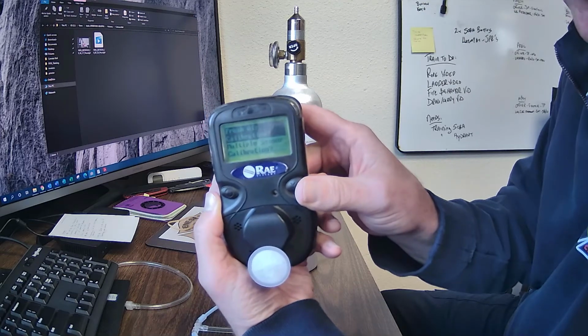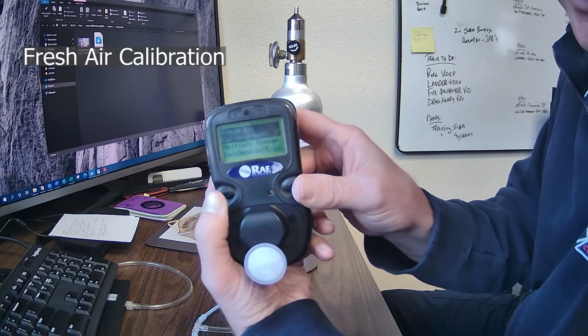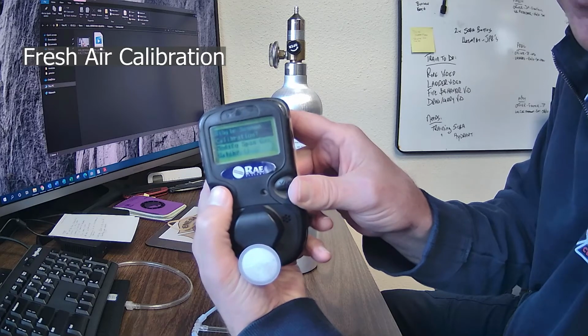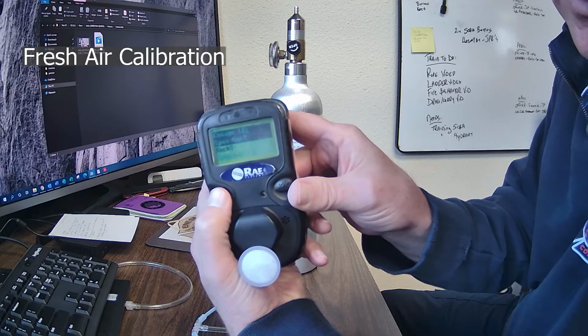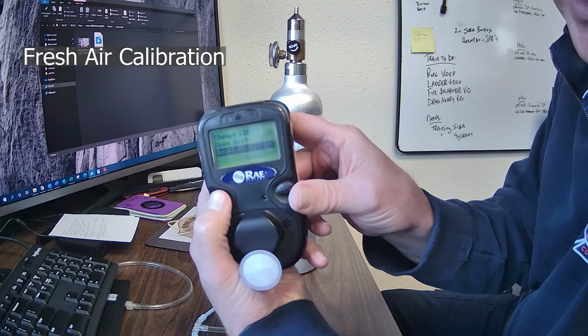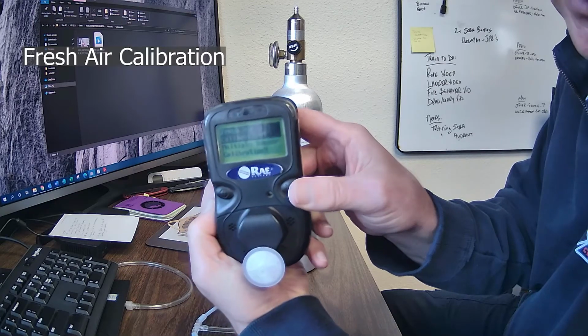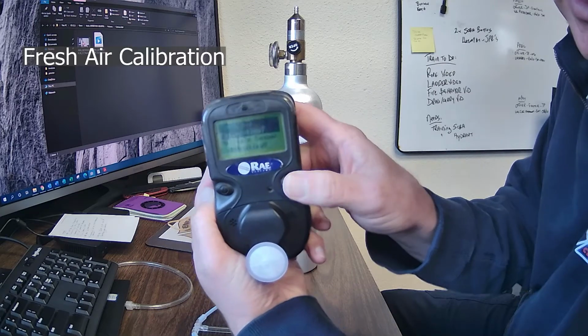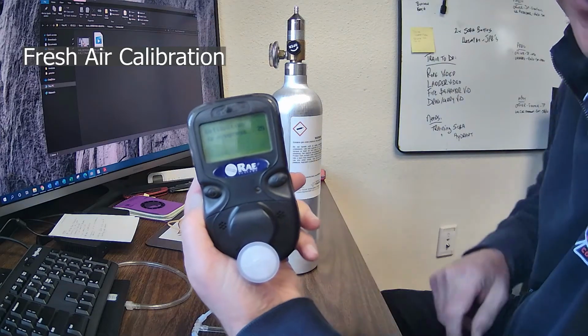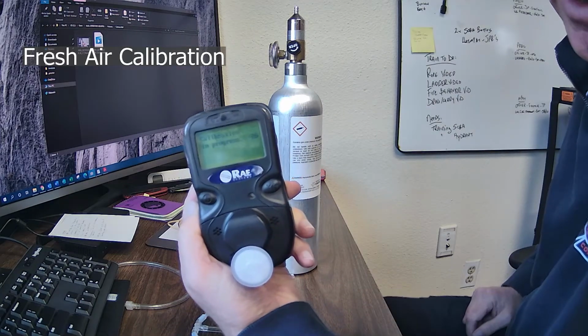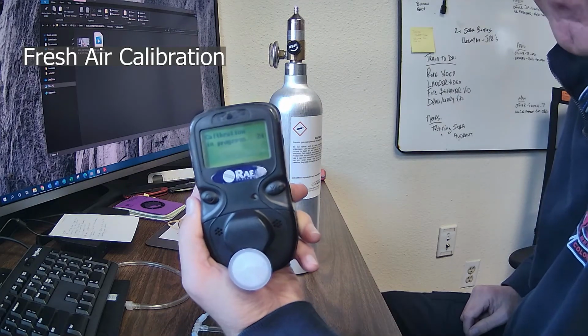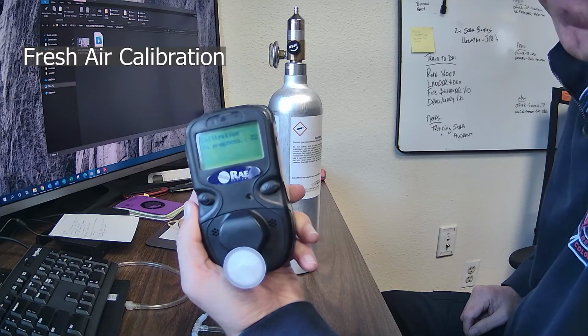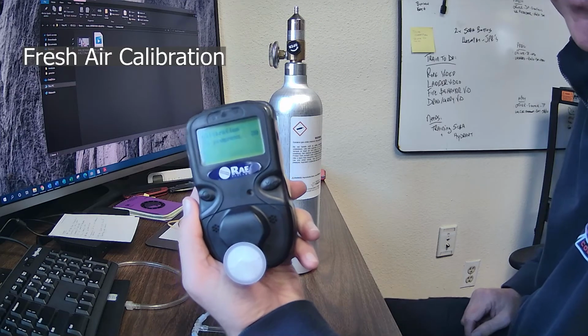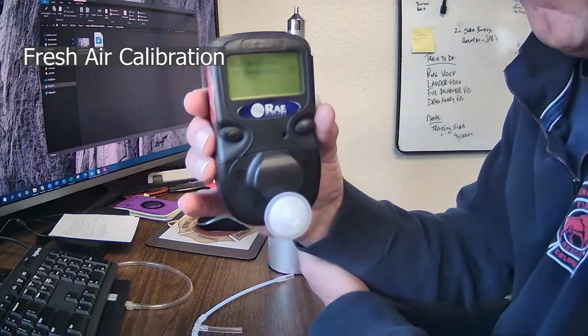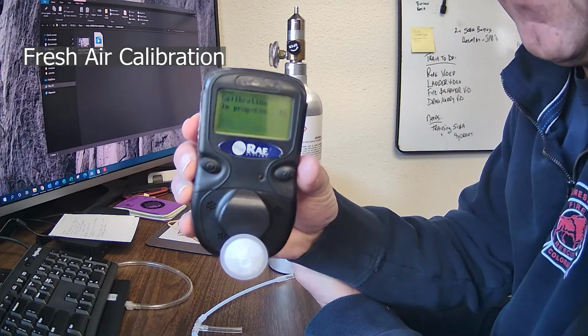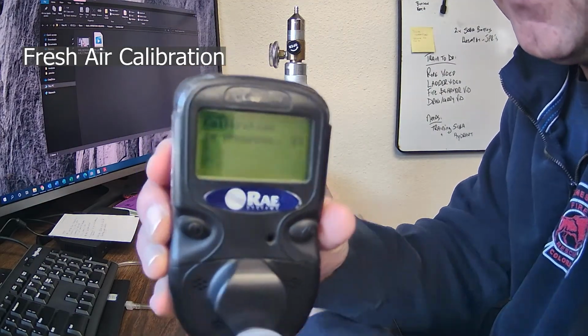The first thing you're going to do is a fresh air calibration. Again, you can scroll down. There's a lot of calibrations that you can do. Or you can say, I don't want to, and go back to the previous screen, but we are going to do it. We're going to do a fresh air calibration, and you leave the filter on while you do it. Always leave that filter on because stuff gets in there and jams the pump. Basically, this is a pump sucking up air. So it ticks down. I'm trying to get it so you can see it, the little reflection. We're at 15 seconds.